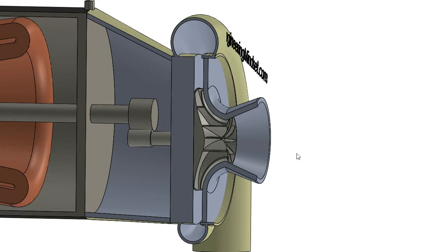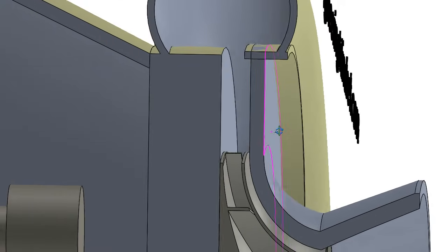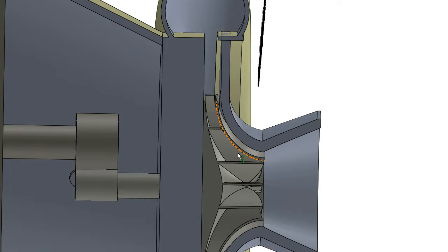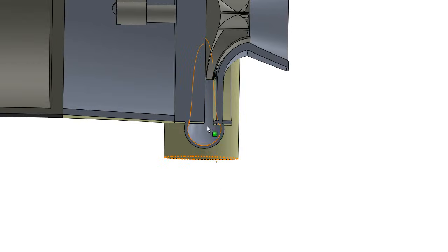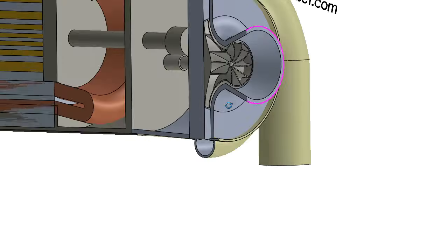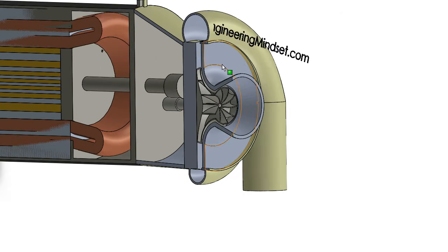Now in this section view you can see the diffuser much clearer. So the diffuser is this thin channel here between the impeller and the volute. See this gap here. As the refrigerant flows into here, and this is spinning at a really high angular velocity, it spins that refrigerant out, spits it out, and then passes through this diffuser before all the refrigerant collects up in this volute, and also obviously down here as well. And it's going to flow like this, round in a spiral shape, round to the discharge line.